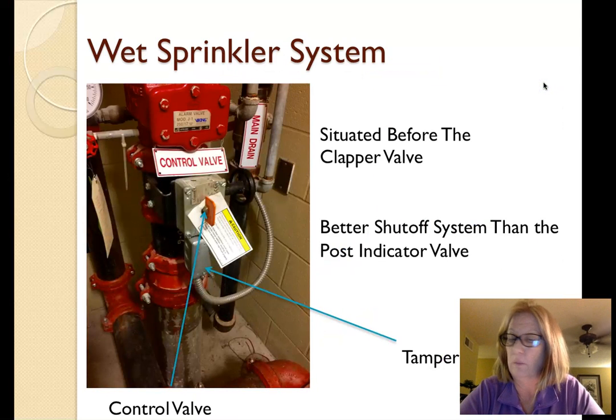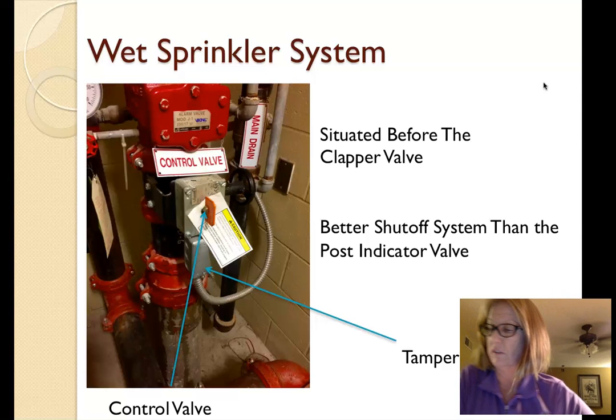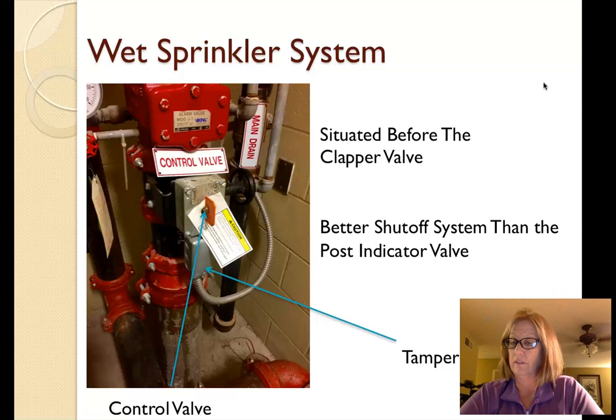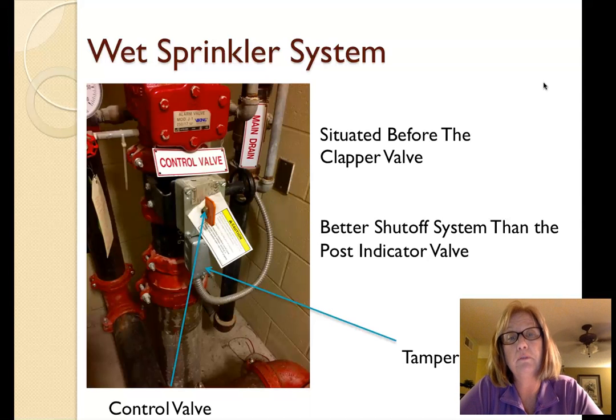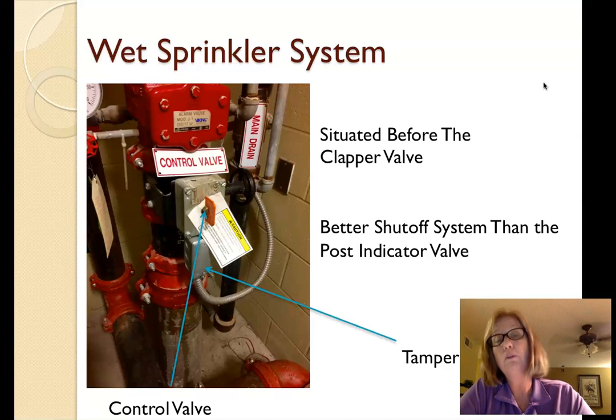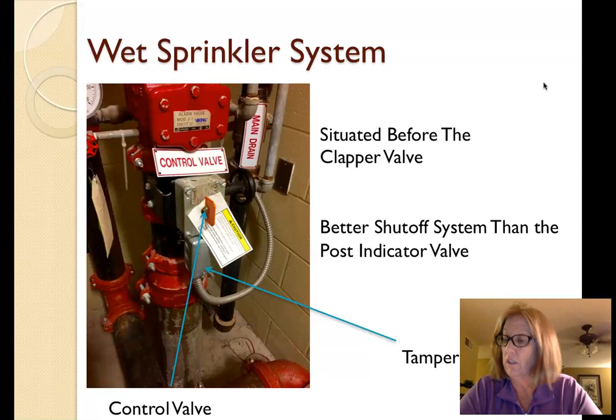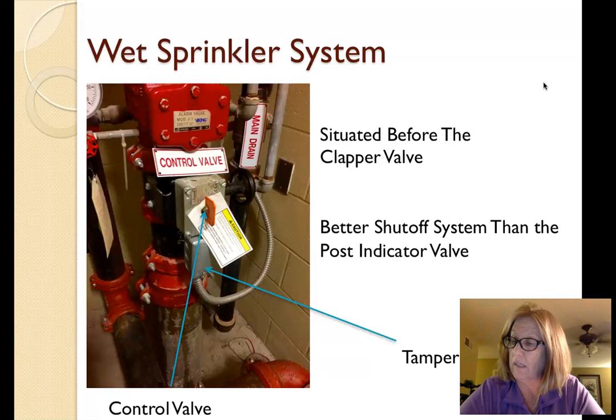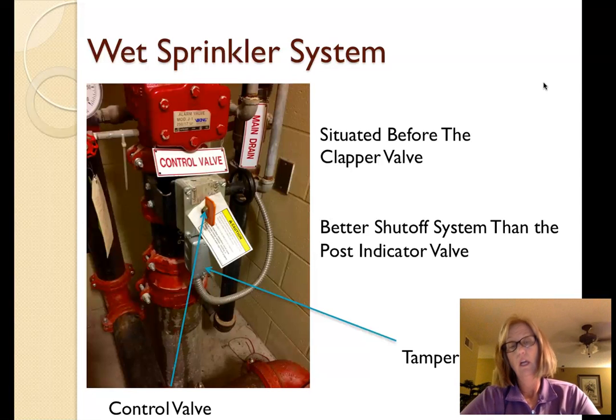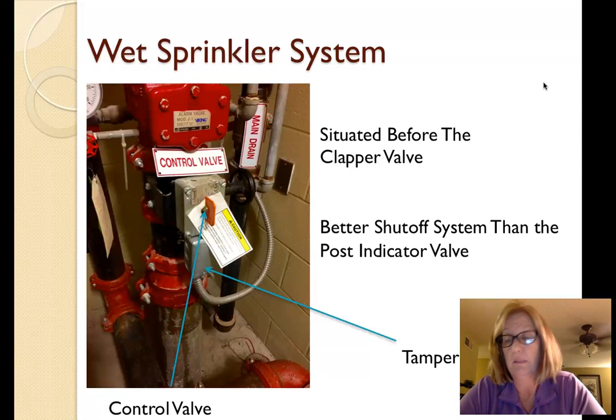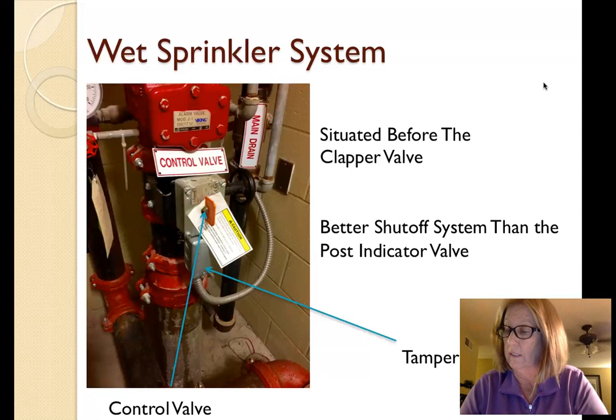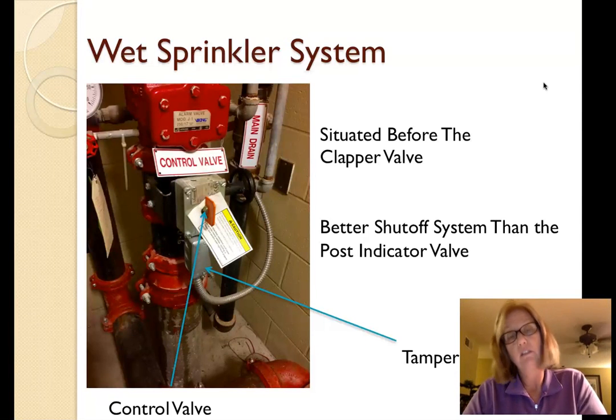The control valve is open on the sprinkler system and situated before the clapper valve on the system. It is a better way to shut off the sprinkler system without shutting off the fire protection water supply to the building through the post indicator valve if maintenance needs to be performed on the system. If the control valve is accidentally kept in the closed position, a tamper switch will send a message in supervisory mode to the panel. After 24 hours, the monitoring company will call the building representative listed to advise them that the system control is in the off position and needs to be opened.